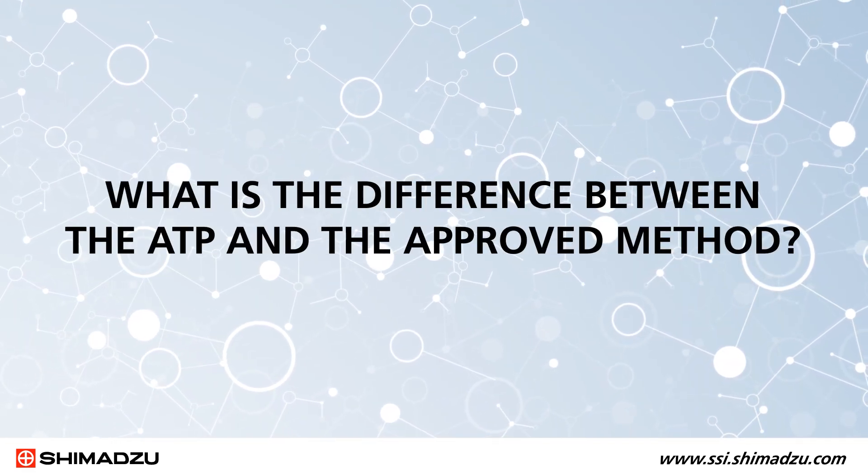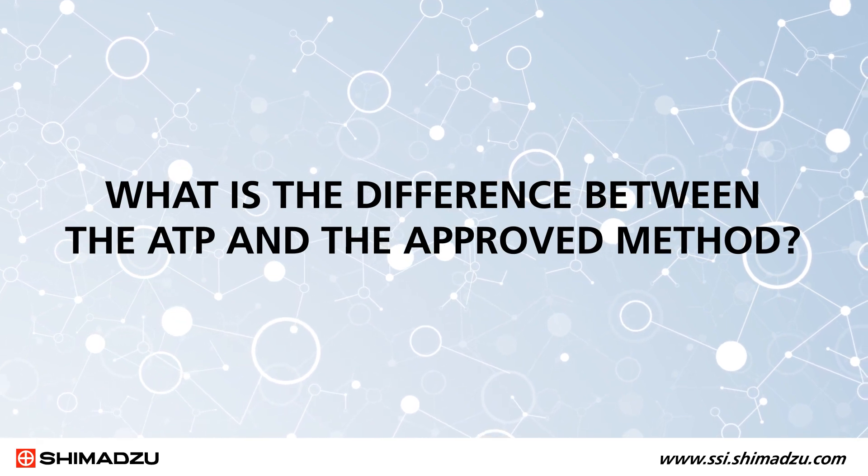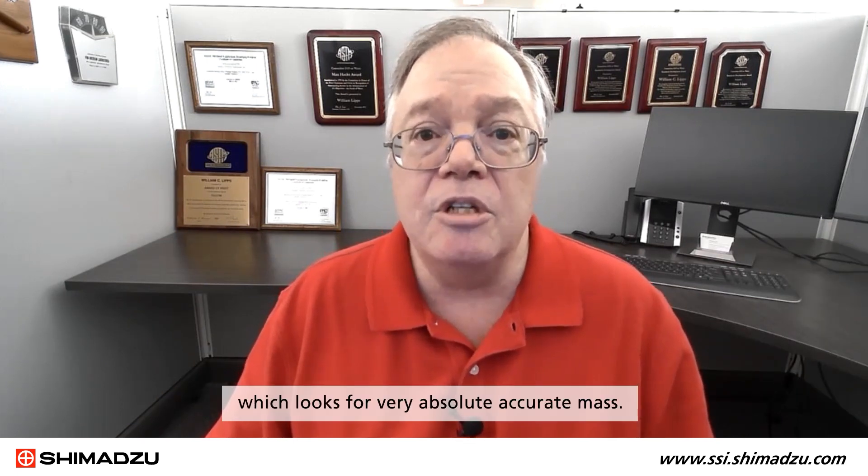The PACE 1613-0-SSI alternative test procedure for dioxins and furans was validated on the Shimadzu GCMS-TQ8050NX. The only real difference between the approved method and the ATP is the detector. In the approved method, you use a high resolution mass spectrometer which looks for very accurate absolute mass. In the GC-MS/MS or triple quad detector, you're looking for MRM transitions.